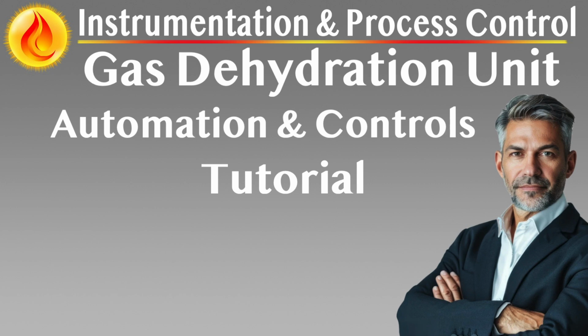Glycol Regeneration Unit Instrumentation and Controls: high-integrity measurement and control for consistent lean glycol quality. Overview. The Glycol Regeneration Unit, GRU, serves as the thermal backbone of the dehydration process, restoring rich glycol to high-purity lean glycol for continuous operation. Instrumentation and control systems within the GRU are designed to monitor, regulate, and protect each thermal and separation stage, ensuring consistent water removal efficiency, preventing glycol degradation, and maintaining process safety.